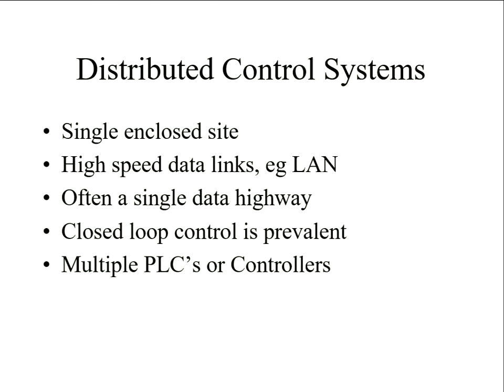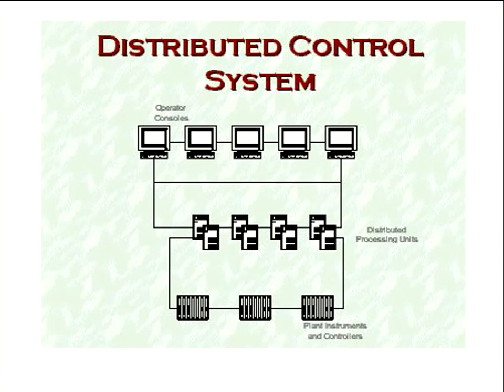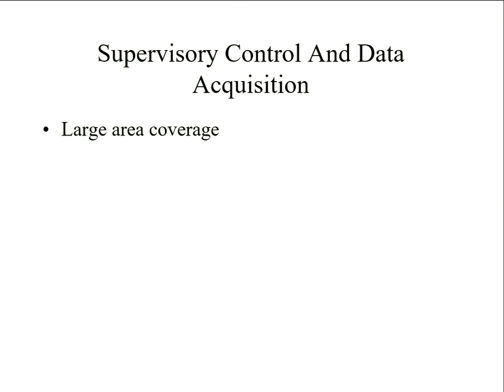So it's a large area. It's gathering in data from all sorts of sources via telemetry, but it's relatively low bandwidth. So you're not doing things at the millisecond level. You're monitoring the broad health of the system. The local control and safety is handled at the site level, where you've got faster update rates. But what you've got is an awful lot of data links. So you're scanning probably hundreds of different sites over time. So it's more of a monitoring exercise. You're not literally intervening all the time. You don't tend to find control loops. Now, the control loops are implemented at the more local level.